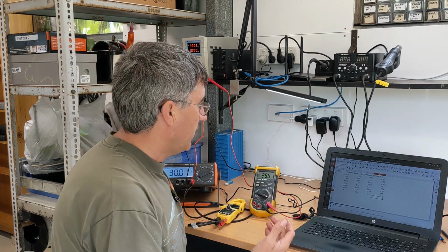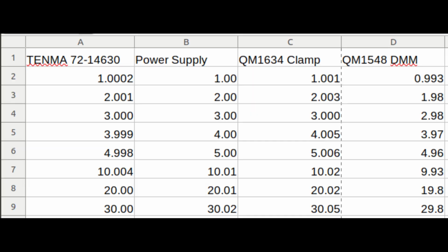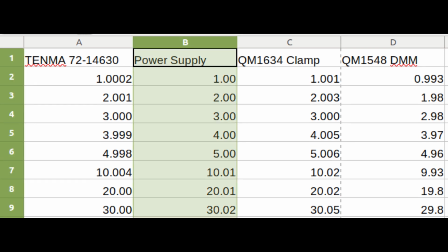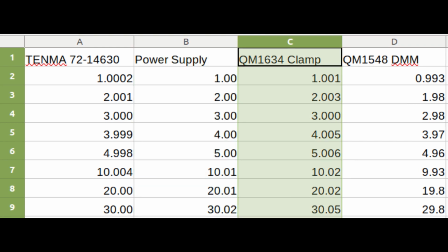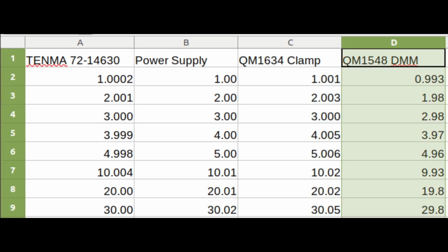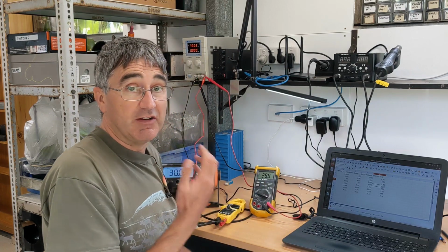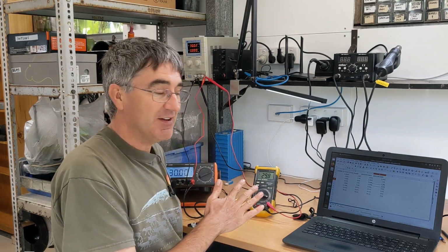Okay, I finished my calibration. You can see from the numbers there that the power supply is reasonably good. It's a lot more accurate than I thought it was because I've always been comparing it with my multimeter, which has not been accurate. My new multimeter, it's actually slightly worse than the power supply at telling me what the voltage is, but it's pretty good, especially compared to my old multimeter, which is a fair way out. It's still, I think, within specification, but only just, and it's not as good as I'd like it to be. So there's my calibration. I can now know how bad my various instruments are.